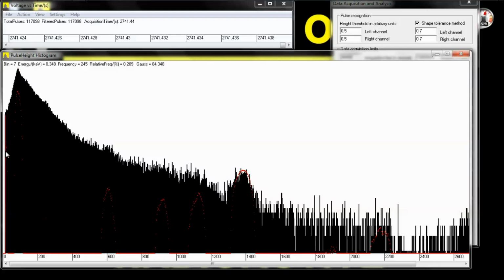And some lower X-ray energy down here. So basically put, it looks like it picked out everything okay. It missed the lead 214 peaks, but they're probably not being generated very fast. So as you can see, with just a little bit of lead shielding, we were able to pick out something. We could determine that this soil sample contains uranium. If we had a lot more lead shielding, specifically lead shielding around the actual soil sample, we'd probably get a much cleaner view. But let's switch to a piece of actual uranium.